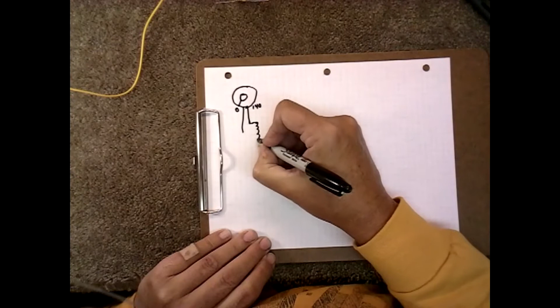So just to give you a pictorial image: I have a Variac that goes from 0 to 140 volts. That Variac drives the primary of my isolation transformer. The secondary of the isolation transformer is a 1-to-1 match. This is a 3 kilovolt amp, 3000 VA transformer—it weighs about 50-something pounds.